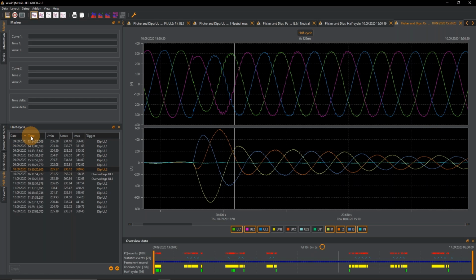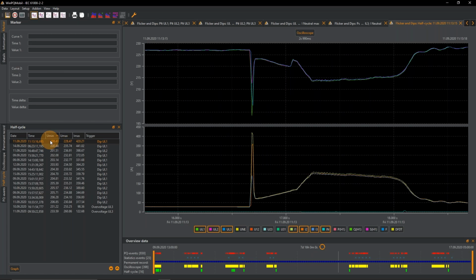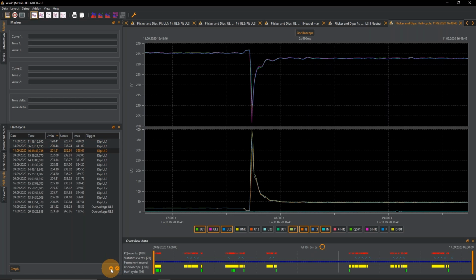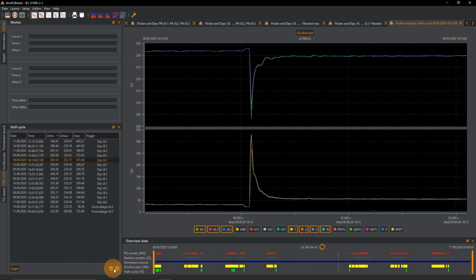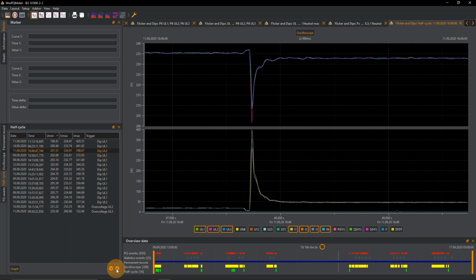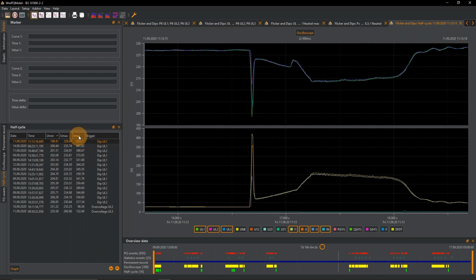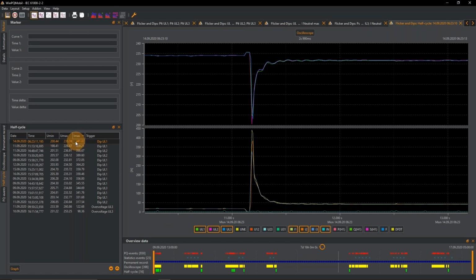So I could sort by date, by time, by minimum or maximum voltage, and I could also sort by the maximum current, ascending or descending. So I will select minimum voltage ascending, and to get the lowest voltage dip with 189 volts. By clicking here, it displays the fault record, and I can simply run through all of the items in the list by clicking the arrow down and arrow up symbol down here, and it just opens me all the fault records. It's a very convenient way to see what was the most severe dip, for example, or the most severe current I had. So if I select the maximum current, that was the one with 441 amps in peak, I can easily select and filter everything within these boxes on here.